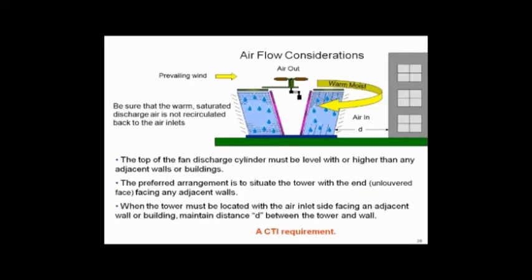Sounds great, right? Now what happens on the air coming to that tower if I do something to the cooling tower like put it up next to a building? Think about it for just a second. If I put it too close to the building and by prevailing winds, as you see in the slide, coming from the left to the right to the building, and I'm kicking out the top of the tower this warm, moist air where I evaporated 15 pounds per ton, so that wet bulb's got a lot hotter than 78 because I'm adding moisture to it. I'm getting that approach close to 85-degree water up there. So I got this warm, moist air coming out the top well beyond design of 78-degree wet bulb. It might even be 82, 83, 84-degree wet bulb.